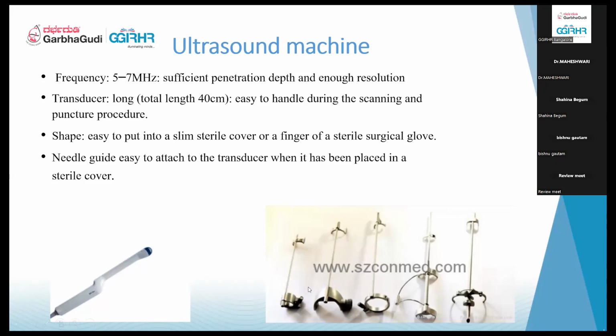So this is another instrument which will be fixed. Can you see all these have a screw here? So with this, it will get fixed onto the probe over here. So these probes will have a groove. On that groove, these needle guides will be placed and they will be tightened. Most importantly, before starting the procedure, you should see whether the needle guide is tightly placed. Check the screw once and then insert the probe. Because what happens if it is not properly tightened, and when you're doing the procedure, if it comes out, then you'll end up puncturing the surrounding structures, which can be very dangerous. So therefore, you need to check all these things prior to the procedure itself.